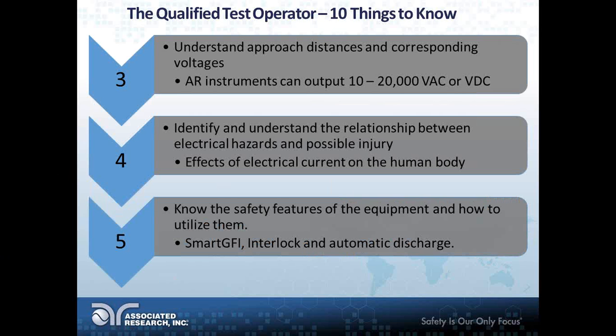What that means is, even if you're a qualified operator, if you get within 2 feet 2 inches of that energized circuit in the 750 to 15,000 volt range, you have to be wearing personal protective equipment in the guise of high voltage gloves, whatever the case might be. If you don't have personal protective equipment, even if you're a qualified operator, you cannot get within 2 feet 2 inches of that energized circuit. And obviously that's for safety reasons.